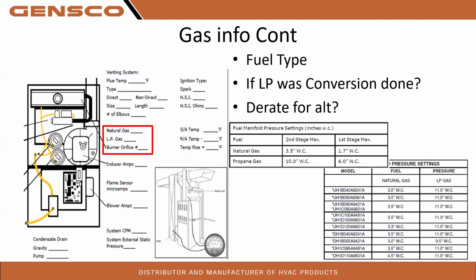So of course we've got different gas pressures for natural and propane. So like first stage on most 40 inches, it's going to be 6 to 10, right? Natural gas is 1.7 to 3.5. And of course they're model specific, right? So in this reference, I'm just using a 40-inch furnace. So we want to know if we have a derate in place, if needed, what spuds maybe, and also if there was a derate for spuds, we want to know. So great data collection.